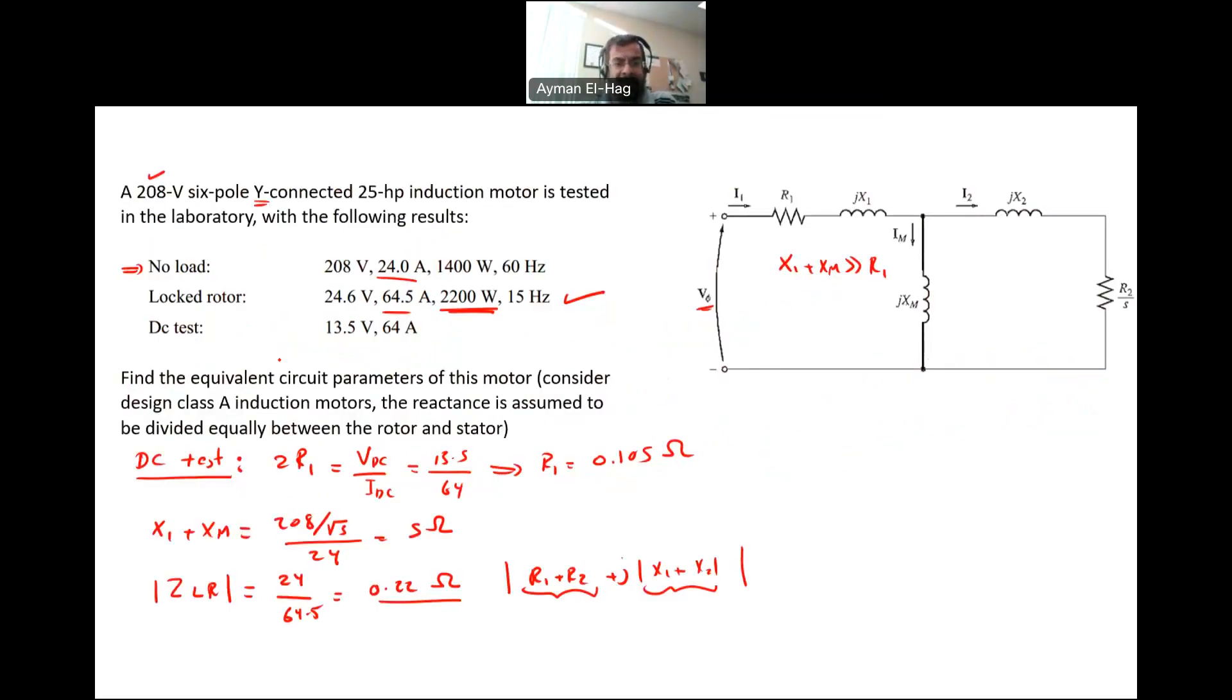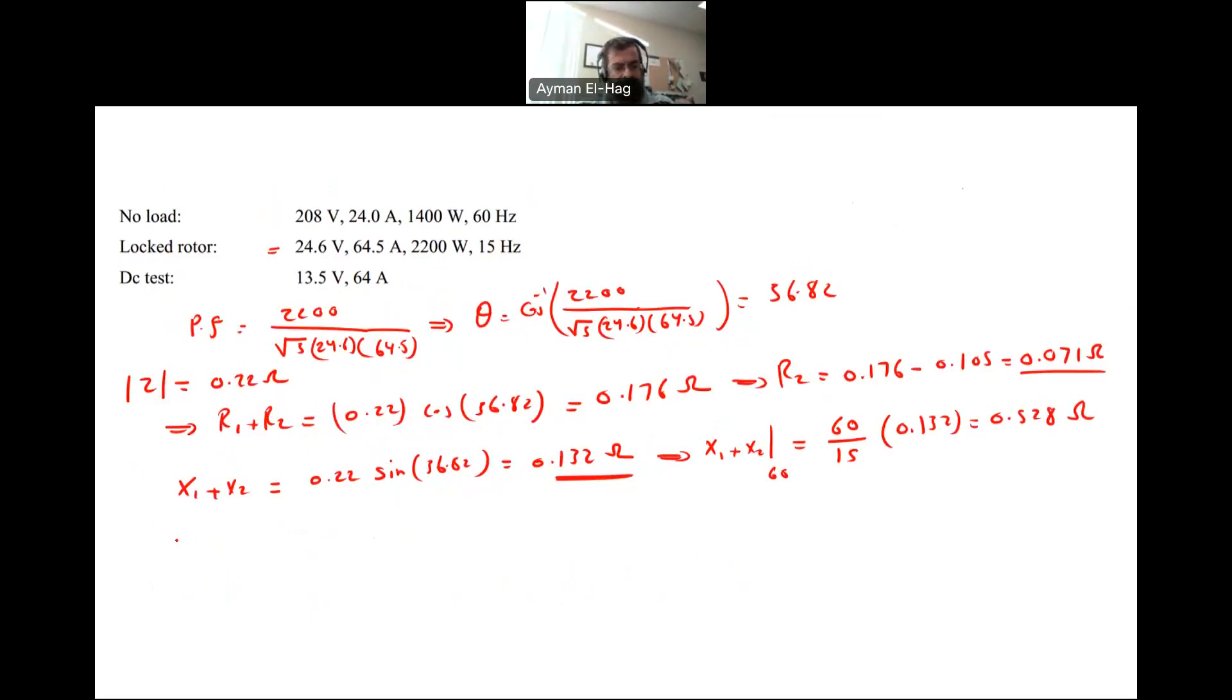If the question says it's a class A, that means the reactance is assumed to be divided equally. So X1 and X2 are equal. X1 equals X2 equals 0.528 divided by 2, which gives me a value for each one of them as 0.264 ohms. I found X1, X2, R1, and R2.